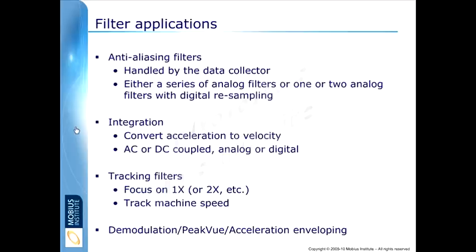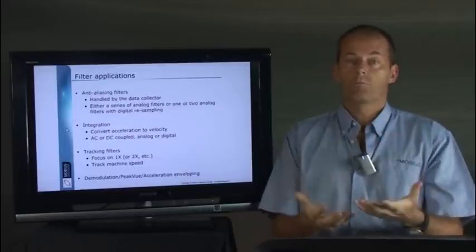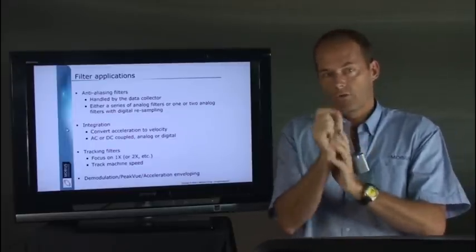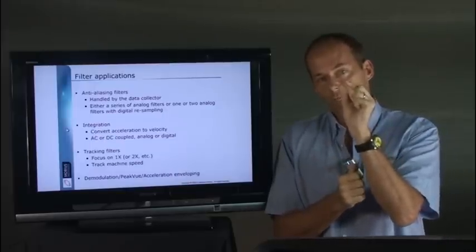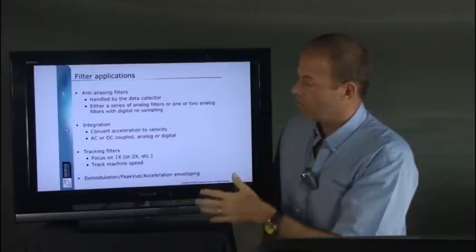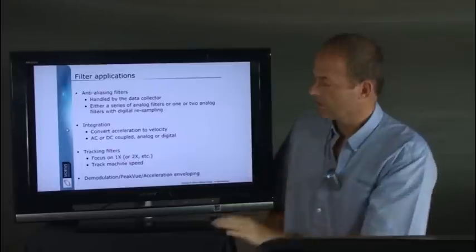Tracking filters, for example, when you're doing tests on, well, there's a lot of applications for tracking filters, but in particular, when you're looking at turbo machinery, you filter out all the vibration other than the 1X vibration. So we just look at the 1X vibration, whatever that is, and that uses a tracking filter. Just the frequency characteristics change as the machine changes speed.